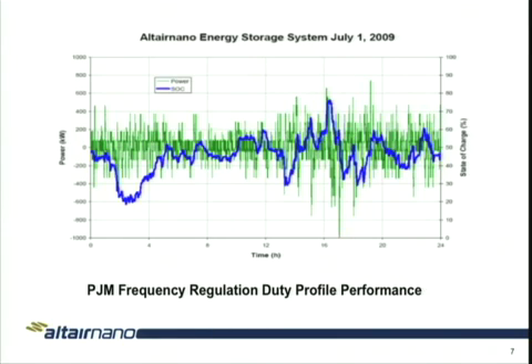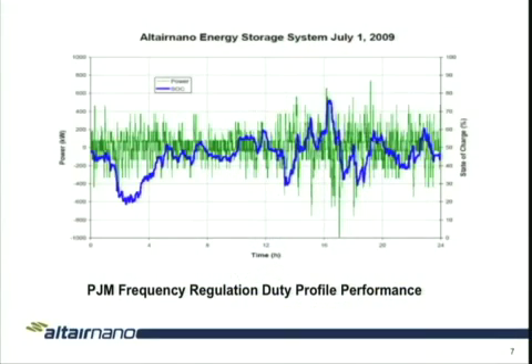And part of that is creating this AGLC, Automatic Generator Load Control signal, that's based off of, here you go, the ACE signal, Area Control Error, that looks at these balancing areas, these regional transmission organizations, and looks at how much power is flowing in or out and maintains that balance. And off of that error, they then create a signal that's sent to all the generators within that transmission organization to either raise or lower their output so that we can have a stable 60 hertz signal throughout North America or throughout the balancing areas.